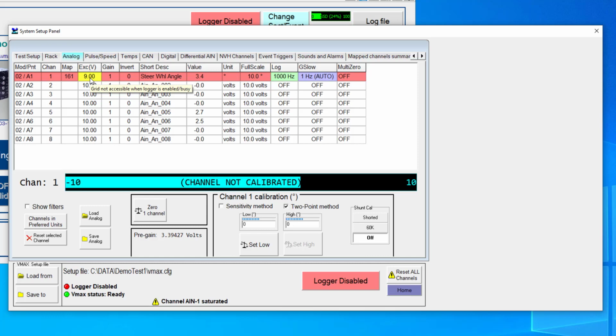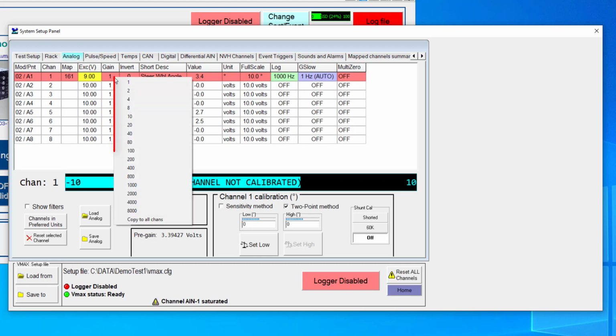Now, the sensors that I'm using here are a high level output. So if I put 9 volts in, I can essentially get up to 9 volts back out. A lot of the sensors that you would interact with on a daily basis, like pressure sensors and things like that, wouldn't necessarily work in that same fashion. Typically, a lot of times those would be a millivolt type output. And when you use a millivolt type output, we would potentially need to use some gain settings here.